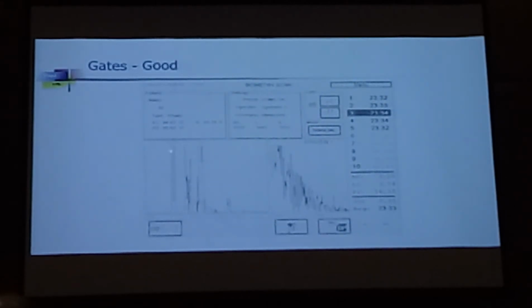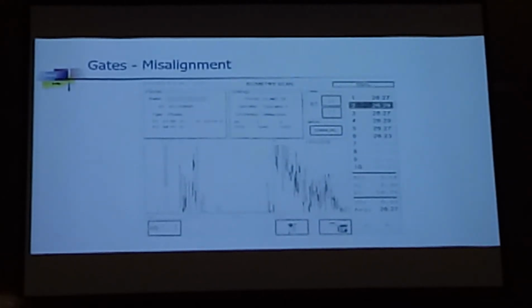This is corneal one, corneal thickness. Like I said, it's an immersion ultrasound because there's a separate spike for cornea. In applanation, this is merged and you cannot actually measure corneal thickness. So C1, C2 is cornea. This is lens thickness, anterior capsule, posterior capsule, and there's actually a plateau before you taper off. So this is a good alignment.